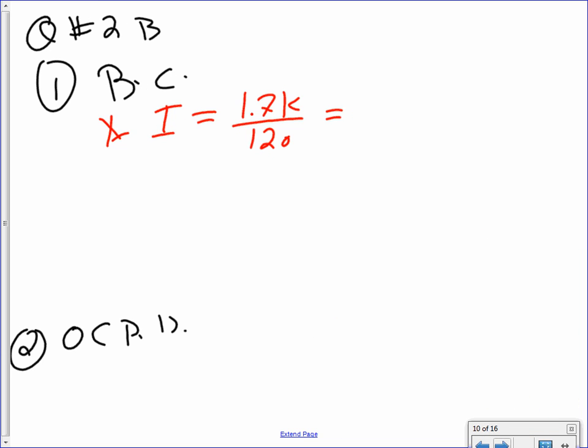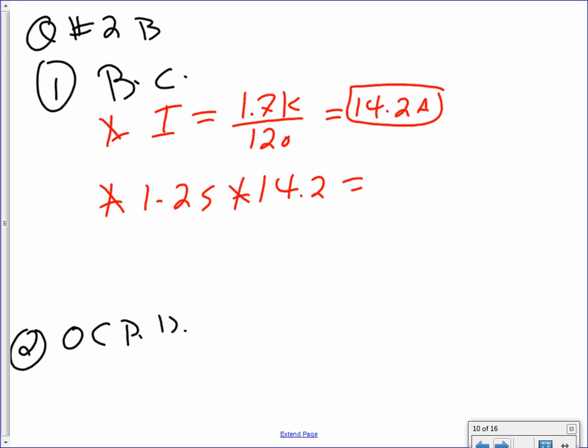Good point. Okay, so then when you do that, you end up with 14.2 amps. Then continuous load, 1.25, multiply this by 14.2, and that gets you 17.75 amps. We should make it 17.8. Let's just do 17.8 amps. I don't like to carry too many digits.